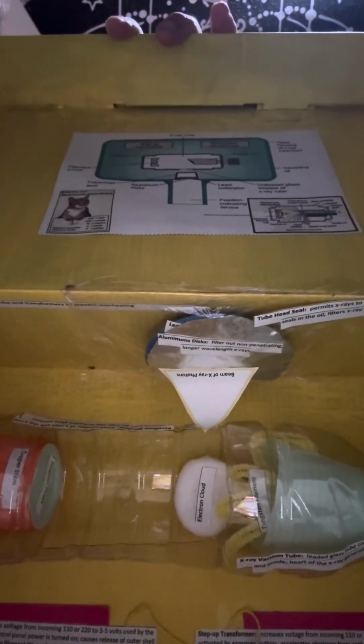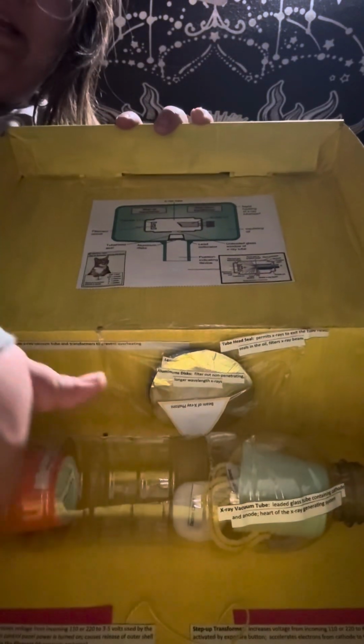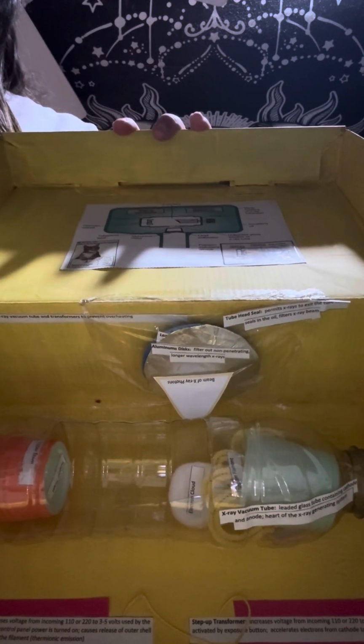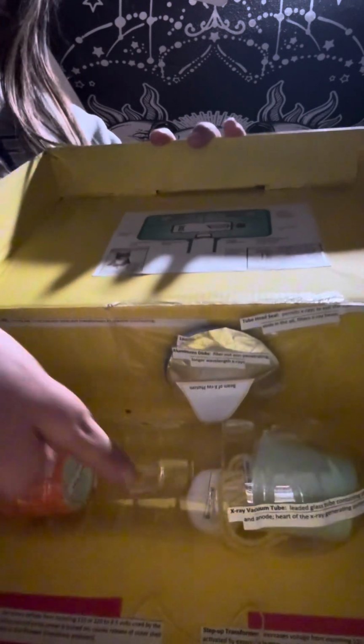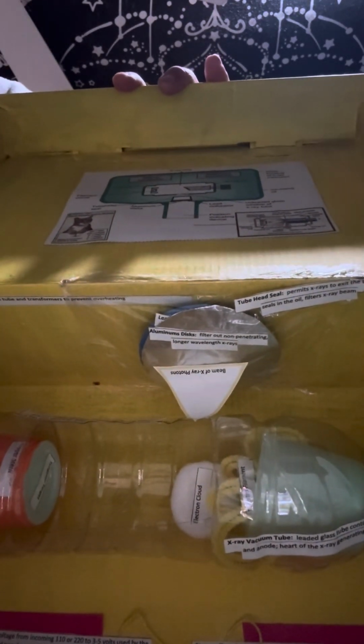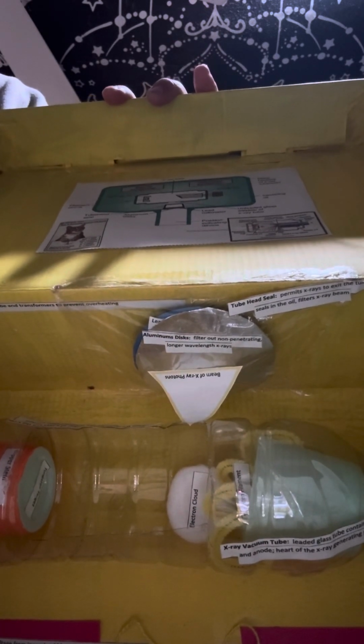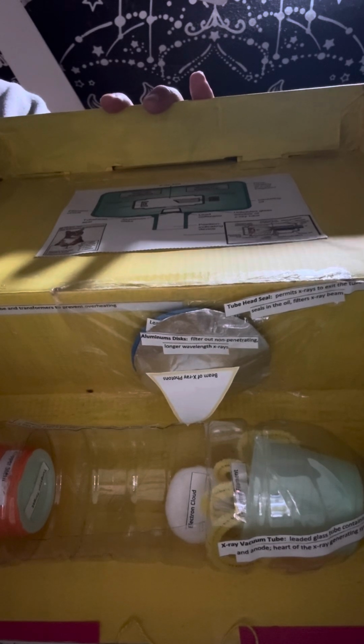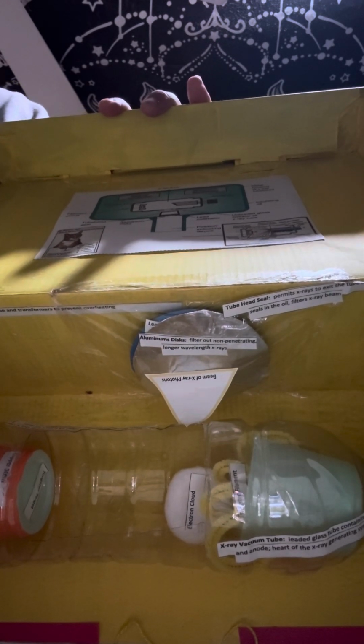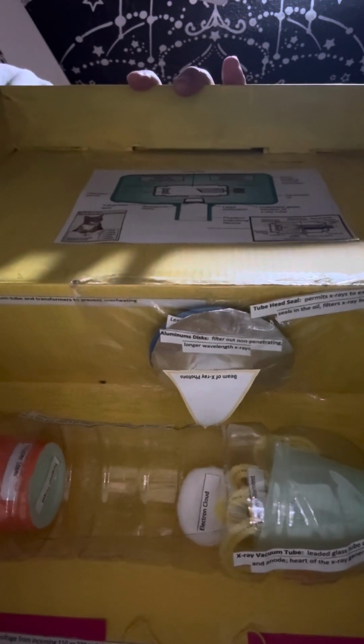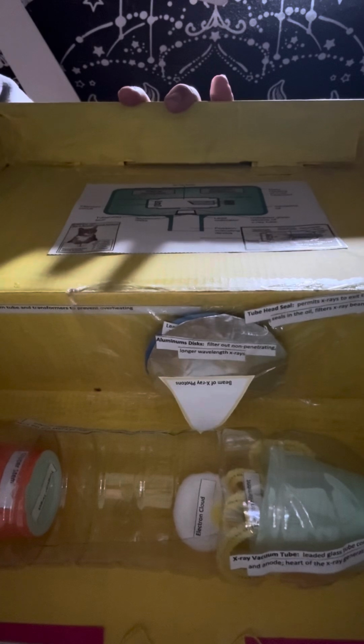Okay, so next we have the x-ray vacuum tube, which is this whole bottle right here, and it is also known as the heart of the x-ray. It is a lead glass tube containing the cathode and anode. And right here, this little hole is called the beryllium window. It is an unleaded glass window where a small number of x-rays exit the vacuum tube. Then we have our filament circuits, which provide power to the tungsten filament and the cathode, which are right here. As you can see over here, our yellow string is hooked up to our transformers, which can provide either higher voltage or lower voltage.